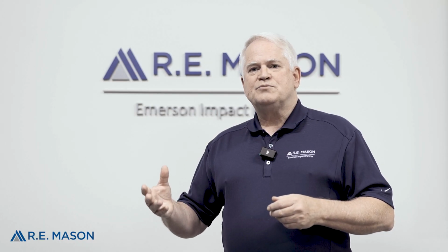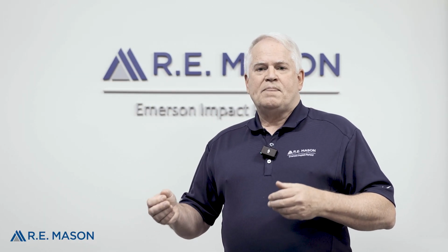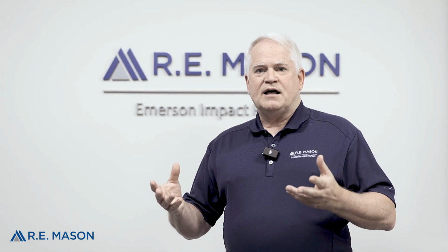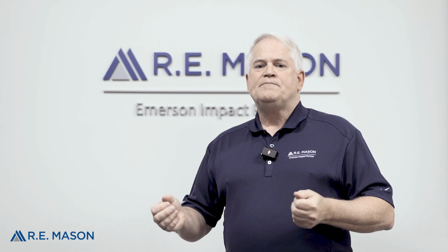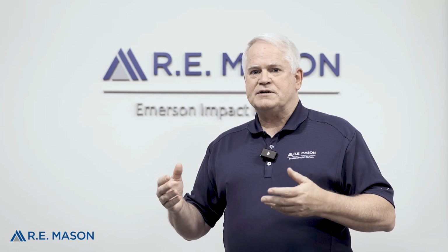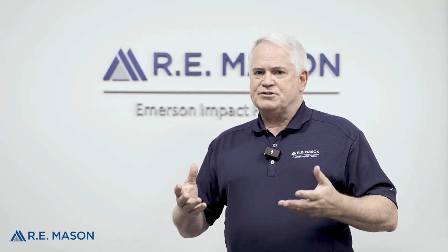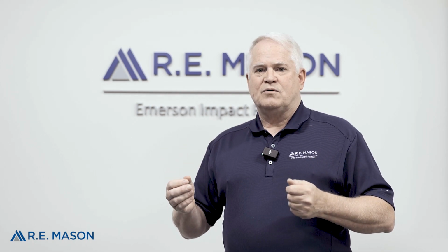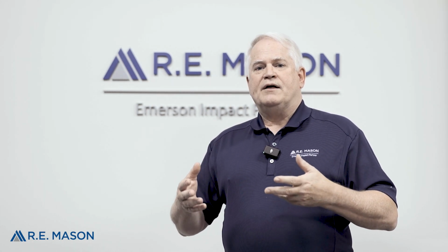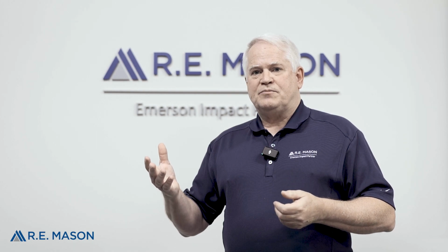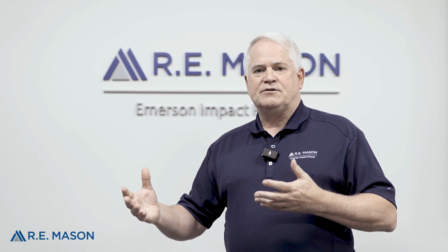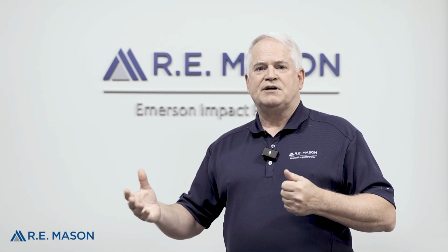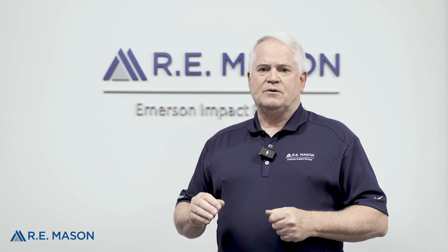There's only a few things we can do about cavitation. Part of it's the design and how we select a valve for it, whether it's going to cavitate or not. There's a cost trade-off because as you get in larger sizes, those globe valves get to be quite a bit more expensive. And then the rotary valves become so much more cost-effective that finding another way to handle the cavitation and potential damage from it is the right way to go.